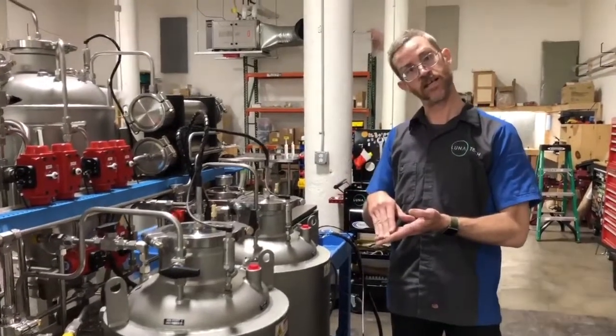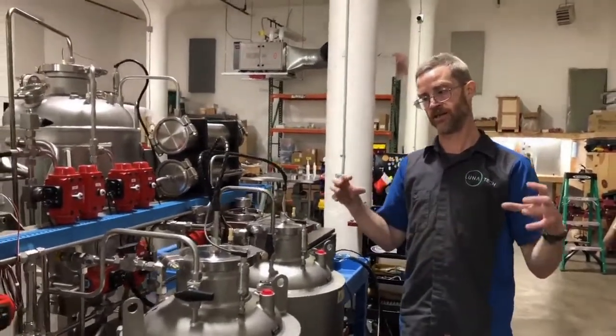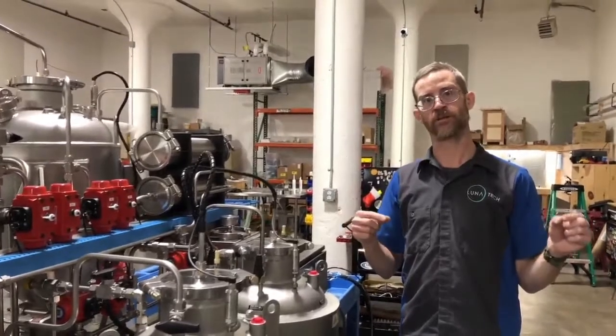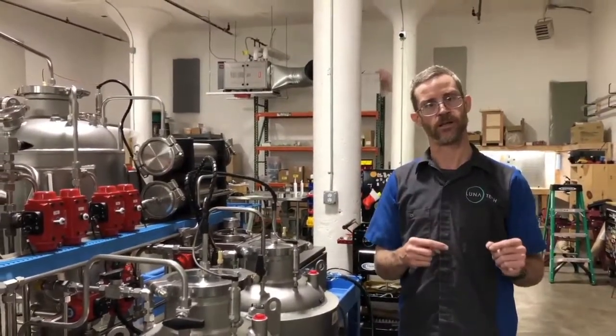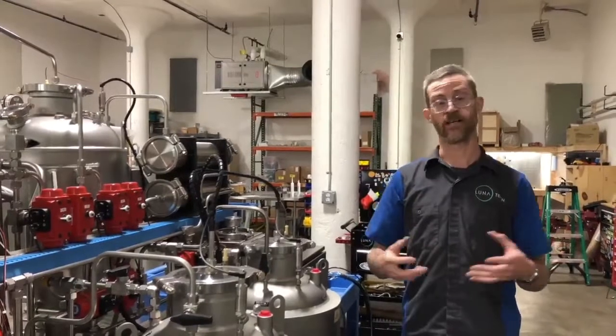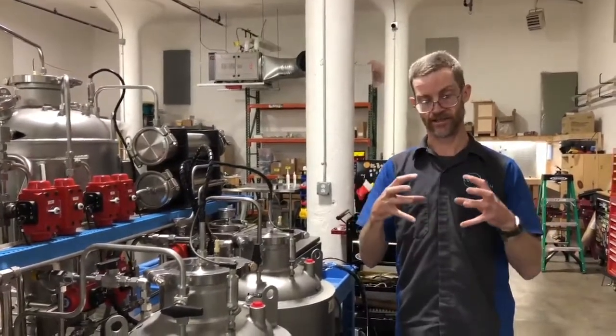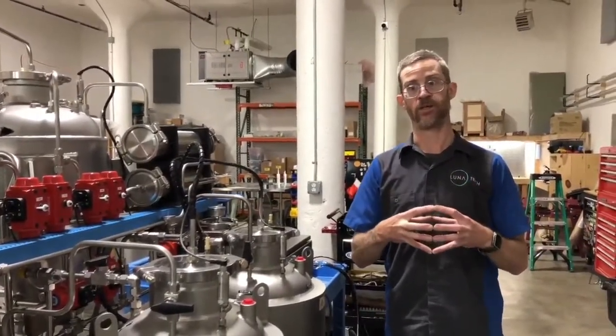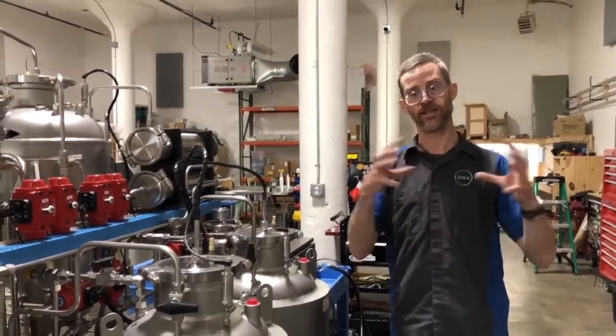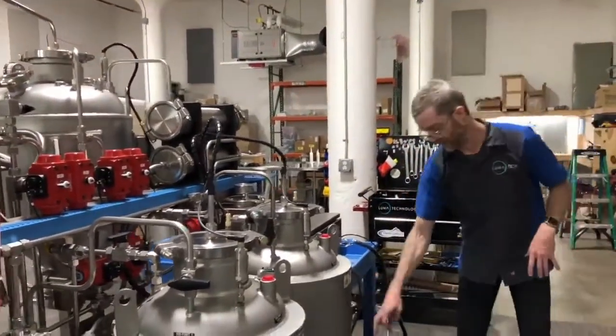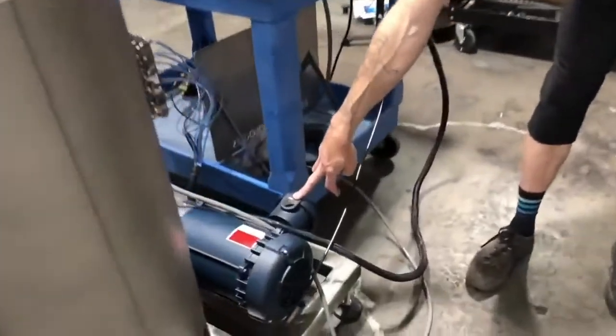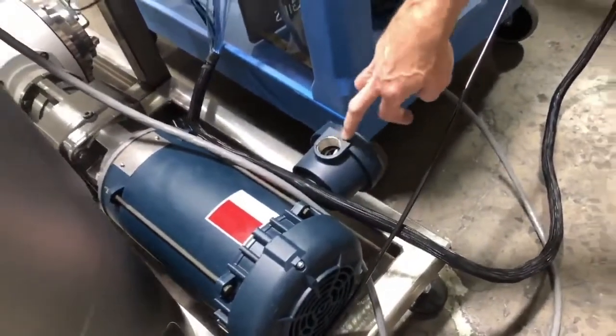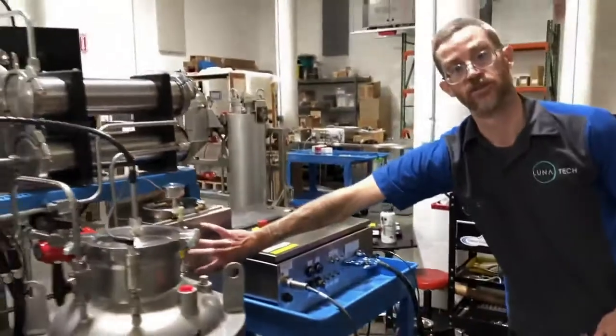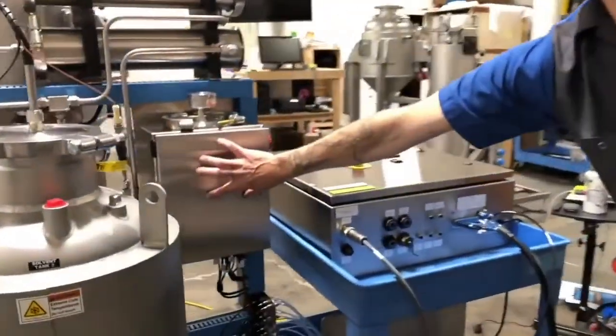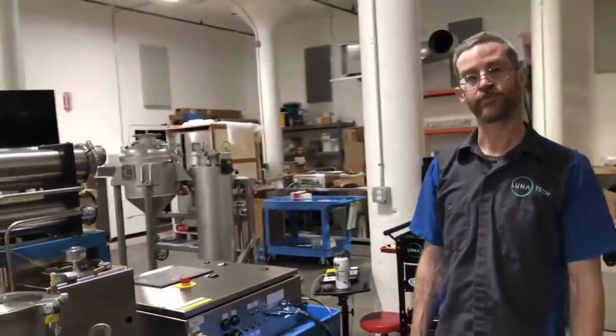So intrinsically safe means that there is not enough current in any of the electrical connections to cause a spark. And explosion proof is just that. Like if a spark does get created, it is contained. So there's no chance for that spark to leave that container. An example of that would be this little electrical connection box here on the solvent pump. This is explosion proof. This is intrinsically safe. A little difference there. All right, can you keep walking us through the sensors?